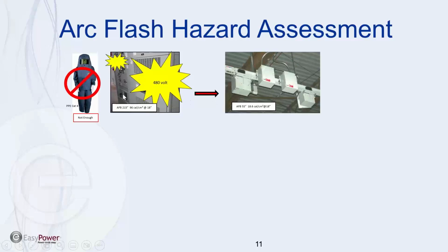Going from one of these main distribution panel breakers to a bus duct, we're down to 18.6 calories. So a suit is enough. If I go up into my aerial lift and change out a fuse, I've got to be in a suit. Of course, if it's a lift and it's your policy to have fall protection on, then you'll need to have fall protection on. And if it's on the outside, you'll need fall protection that's arc rated. So you're going to have to be careful about making sure you have the right equipment for that.